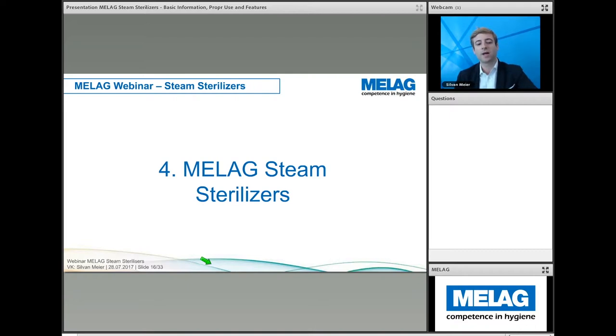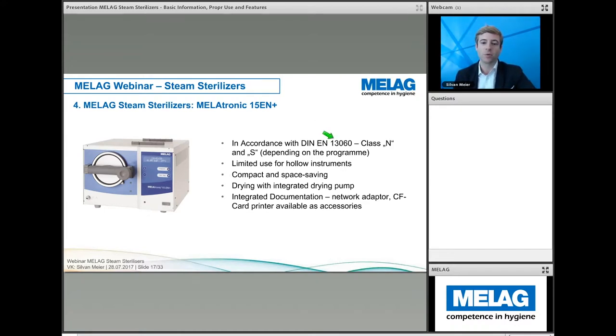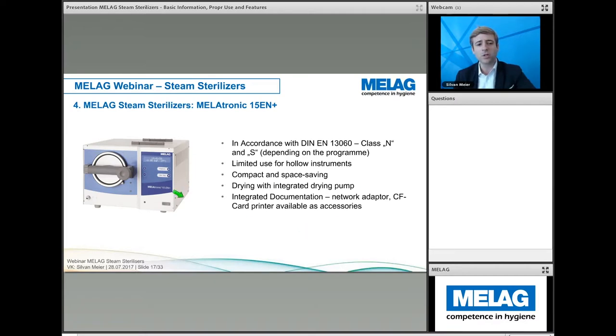The Melatronic 15EN+ complies with EN 13060 and has both N and S class programs. As mentioned, hollow instrument use is limited — only unwrapped, solid instruments are recommended. The autoclave is compact and space-saving, with an integrated drying pump for efficient drying. Documentation is possible through accessories such as a network adapter, CF card, and printer.